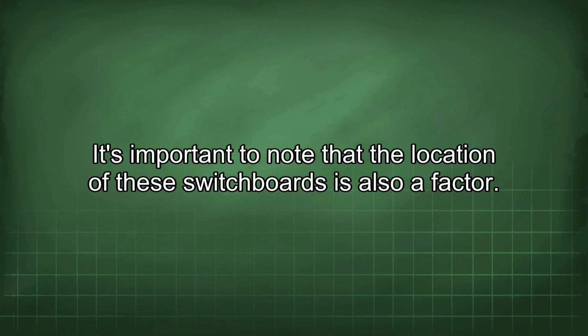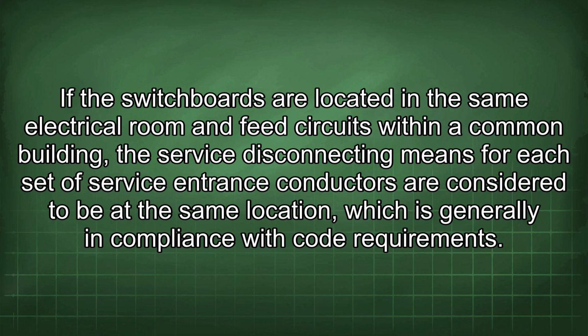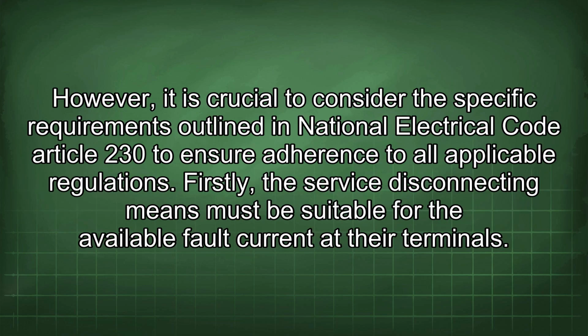It's important to note that the location of these switchboards is also a factor. If the switchboards are located in the same electrical room and feed circuits within a common building, the service disconnecting means for each set of service entrance conductors are considered to be at the same location, which is generally in compliance with code requirements. However, it is crucial to consider the specific requirements outlined in National Electrical Code Article 230 to ensure adherence to all applicable regulations.